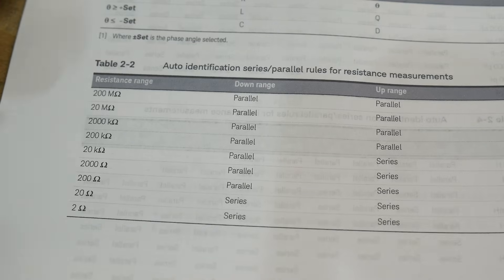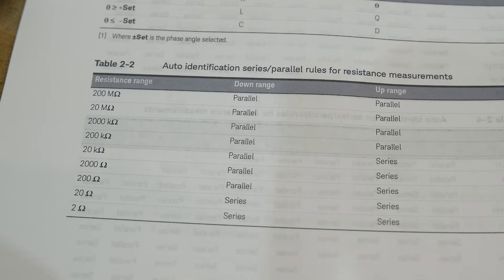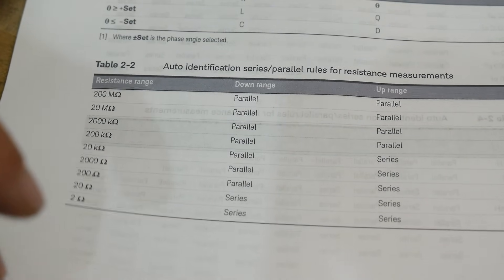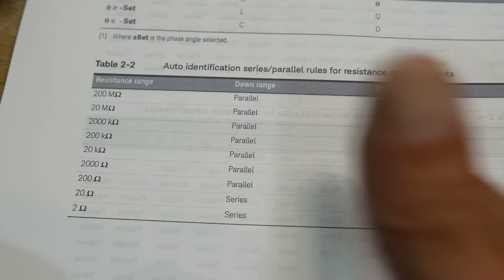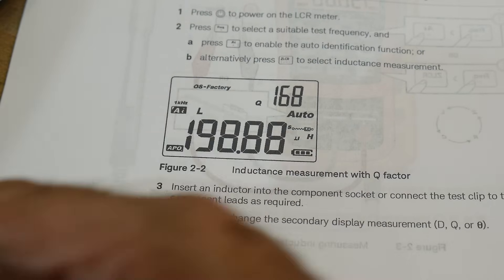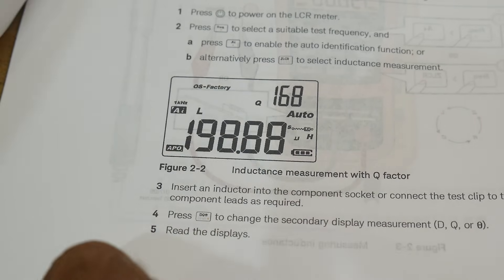So even though you would think it wouldn't matter with the resistance, the calibrations and stuff are better with one mode or the other, because they are different mathematical models inside of the device. So when you do the open short calibration, it does store those cal datas differently for the series and parallel.